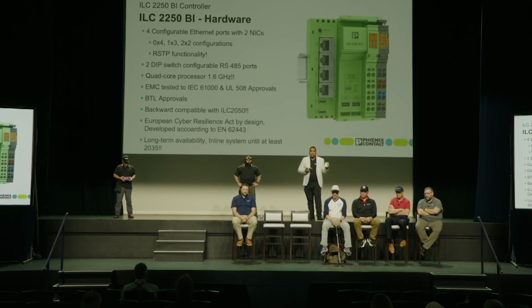It's also backwards compatible, so any of our customers who have used the 2050 controller - if you want the new quad-core CPU controller, you just replace that existing controller with the ILC 2250 controller in its place. It will still mean the I/O modules you use will still work with the new controller. No need to change your I/O modules.